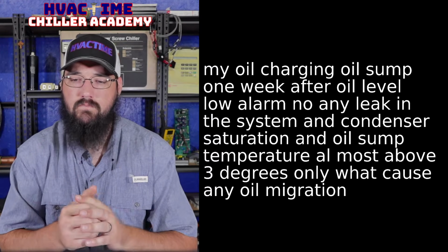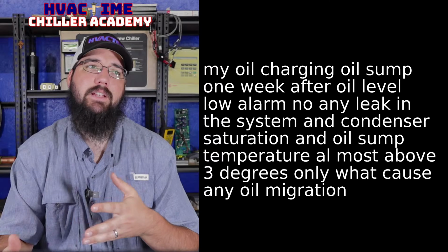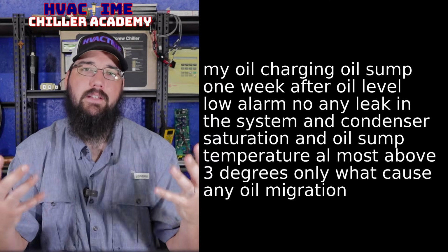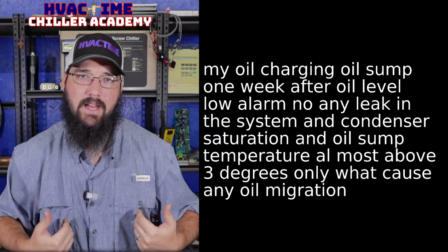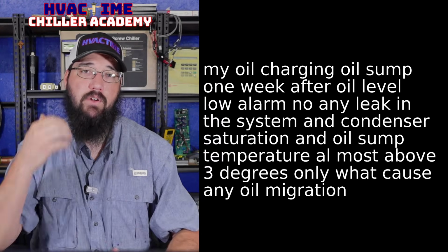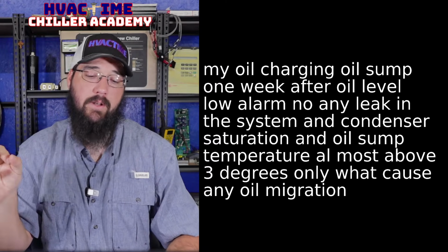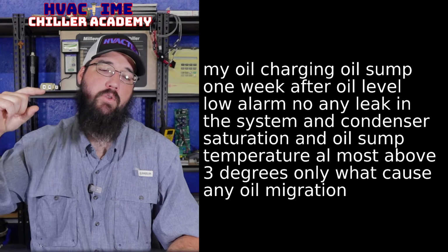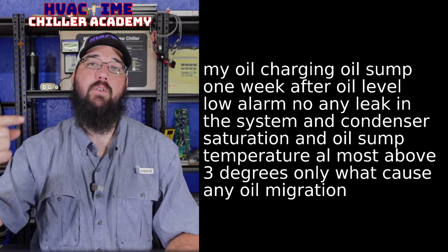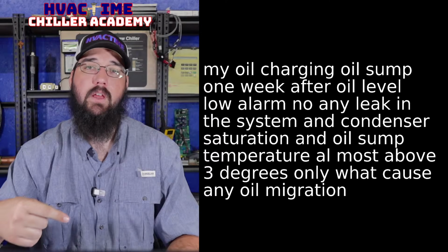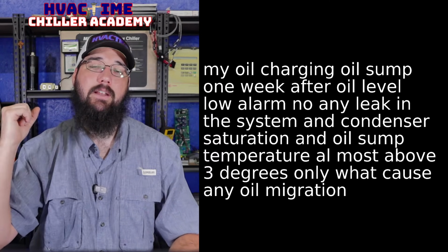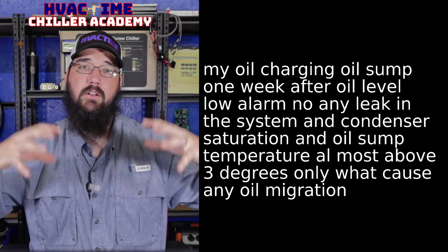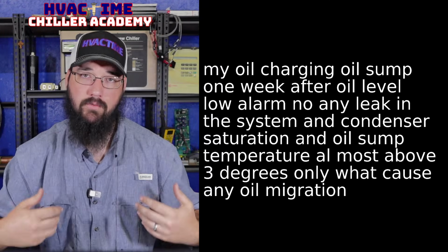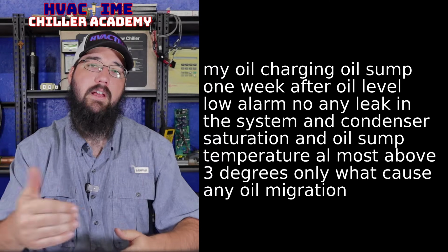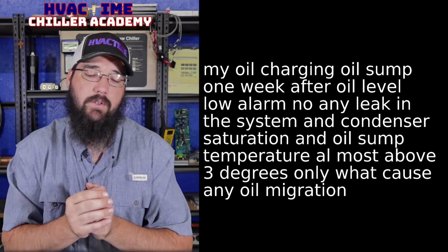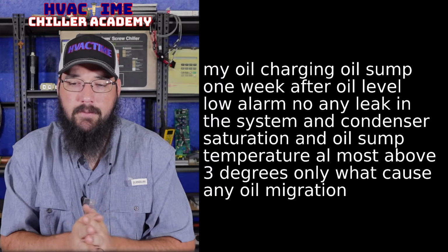So it's just a matter of trying to get that circuit online and get the DP up fast enough to get that oil to return before we start having faults and issues. And it's very, very, very common in low ambient scenarios that you may have to cycle that circuit and let it trip on that oil fault a couple of times before it finally will come on, and then it's got enough oil to return from the couple of startups it's had. It's had just enough oil come back, and then it can stay online and keep the compressor safely running with the oil circuit. So just some stuff you may run into with that.